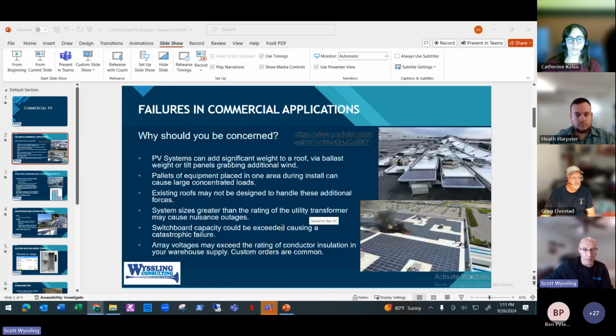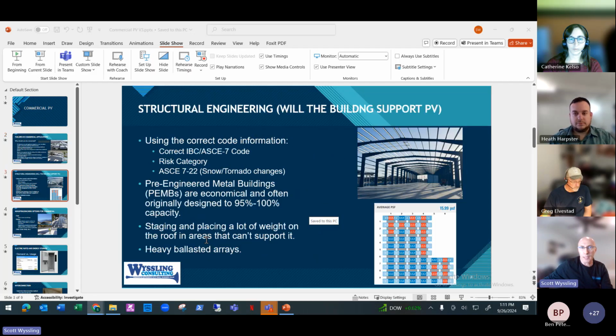Without that information, switchboard capacity could be exceeded, causing catastrophic failure, and array voltage may exceed the rating of the conductor insulation in the warehouse supply. These are really important things to be aware of in commercial applications.